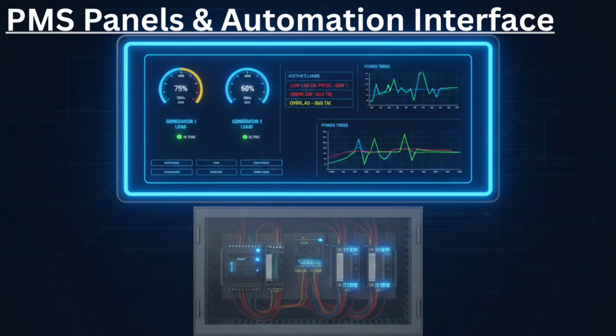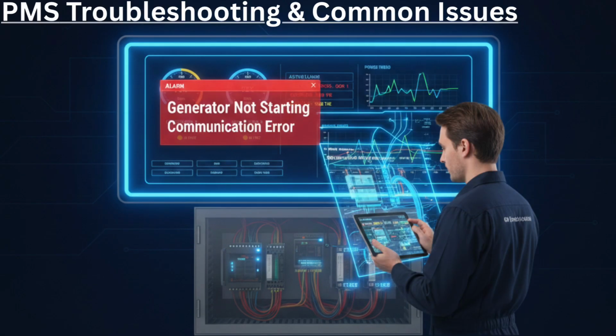PMS troubleshooting or common issues. Even automated systems can face problems. Common PMS issues include generator not auto-starting, synchronization failure, load imbalance, false load shedding, and PLC communication errors. Troubleshooting involves checking sensor signals, CTPT inputs, governor or AVR settings, and communication cables.